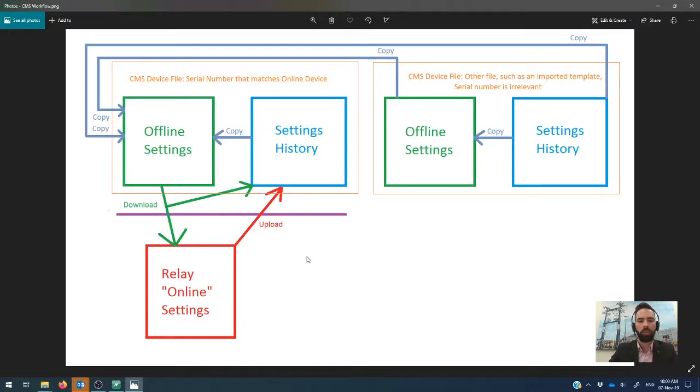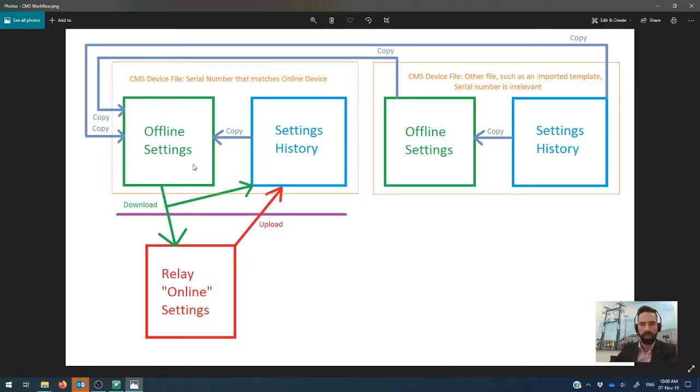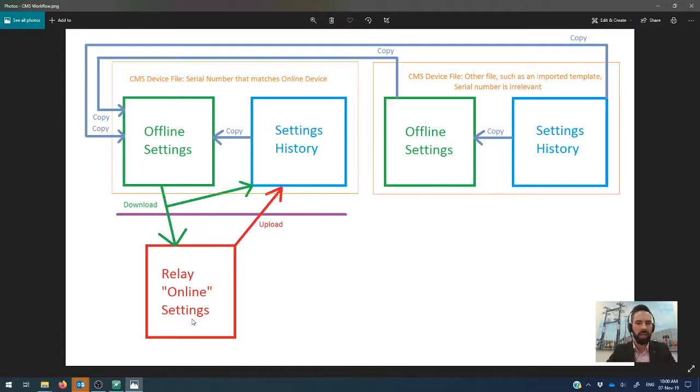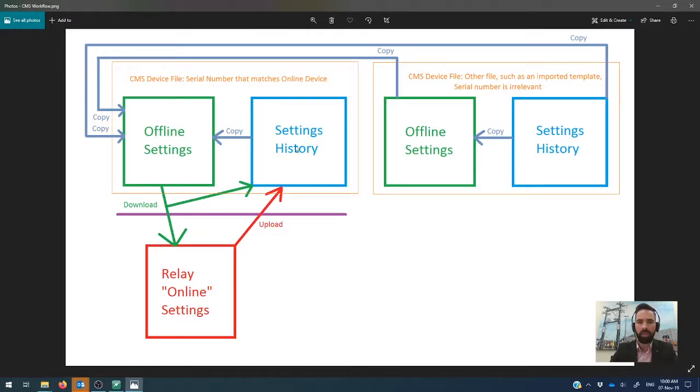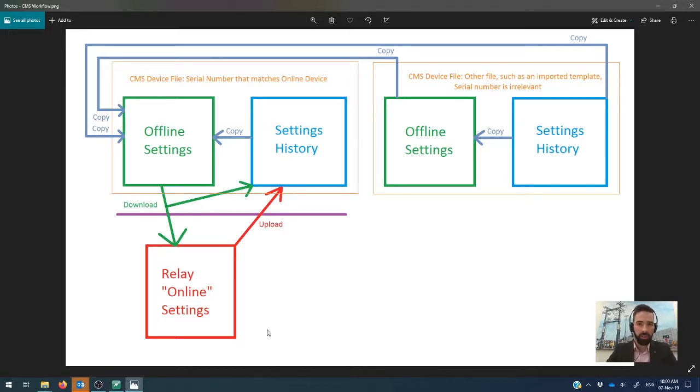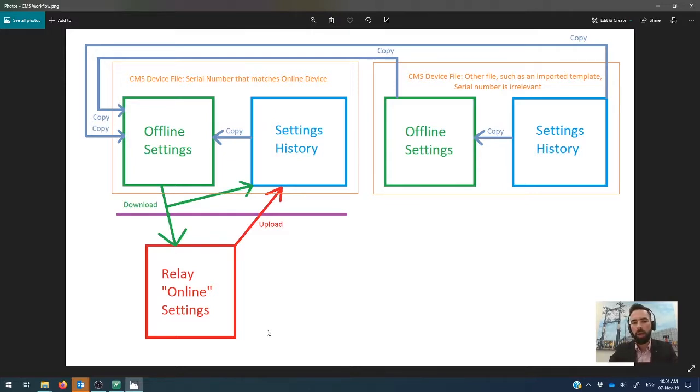So you've got to remember this time around that when you're pushing settings into a controller, it's a download operation because you're downloading it to the relay. And if you're retrieving settings out of the relay into CMS, then you're doing an upload out of it. So whenever you do a download from your offline settings into the relay, a copy of the download is saved in your settings history. And if you do an upload, which is something I recommend the first time that you ever go out to one of these devices in the field, just so that you've got something that you can refer back to in case you want to revert back to the settings as what they were when you arrived at the site, they live in the settings history too.